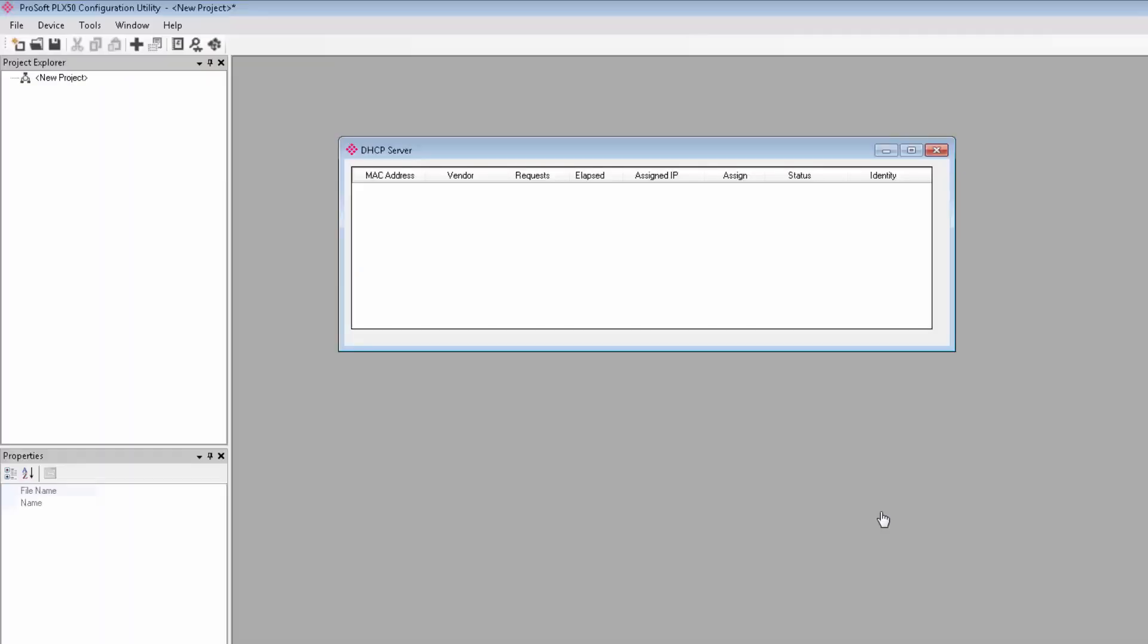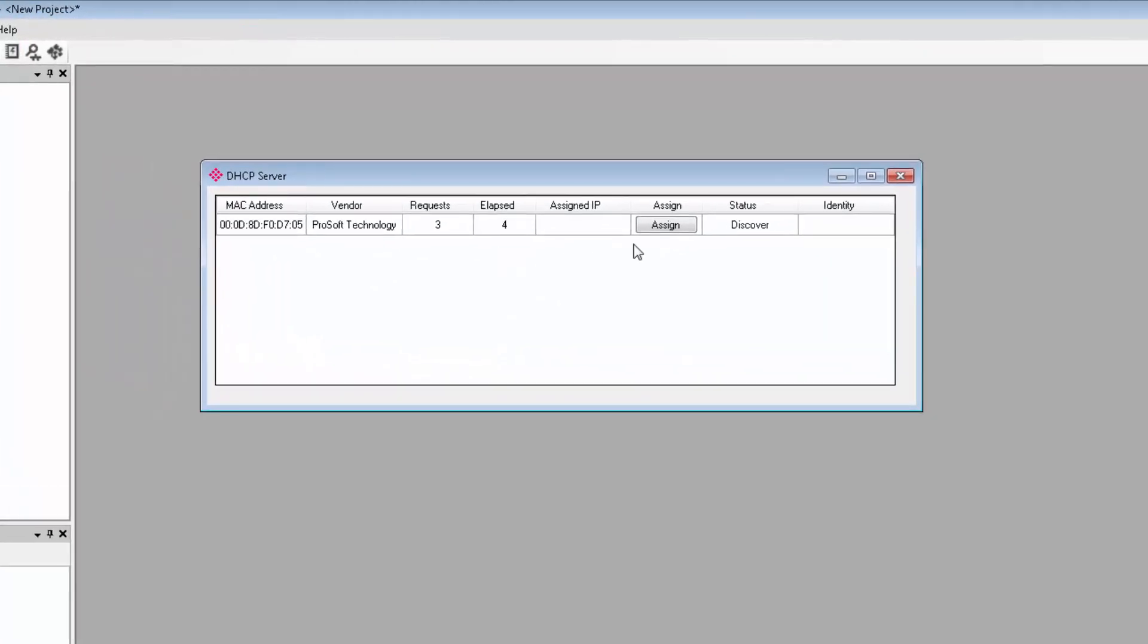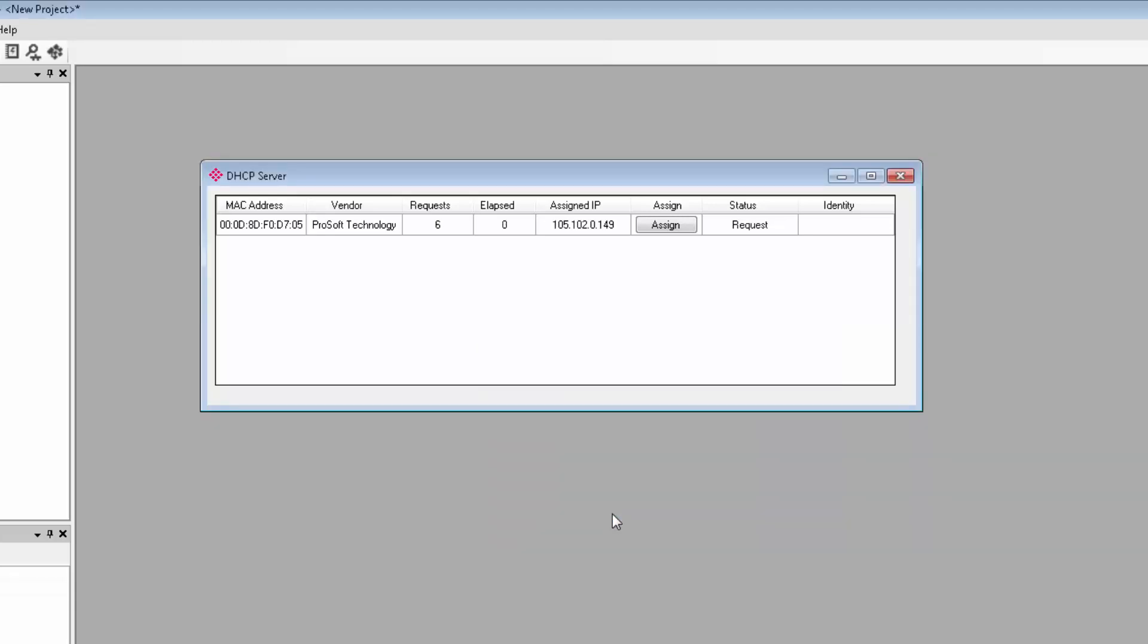The first time you connect the Data Logger Plus module to your network, you'll need to launch the DHCP server and assign it an IP address on your subnet. You need to take care not to connect the gateway to a network with its own DHCP server, although that can work and we'll get to that in a little bit. So you click this button here in the menu bar and there is our gateway. Click assign and on the window that opens, I'll enter an IP address that I know is available on the local network. Select enable static and click OK. The bar should turn green, letting you know that the gateway has been assigned the IP address and is now connected.